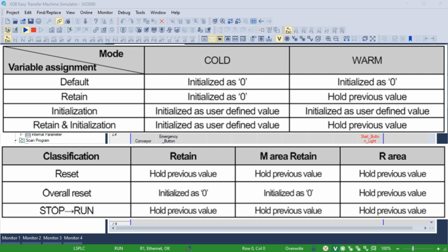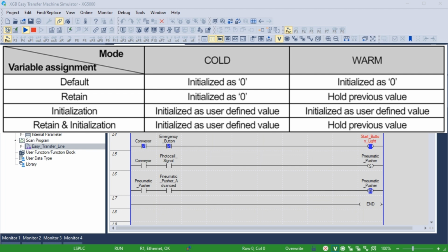Initialization of data. If the PLC becomes clear memory status, the memory of all devices is deleted as 0. When you want to specify the initial value, use the initialization task at the CPU module. There are 2 types of built-in memory. One is program memory to save programs made by the user for the user to construct the system. Another is the data memory device area, saving data during operation.